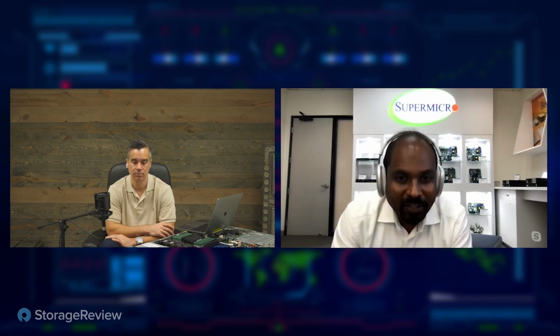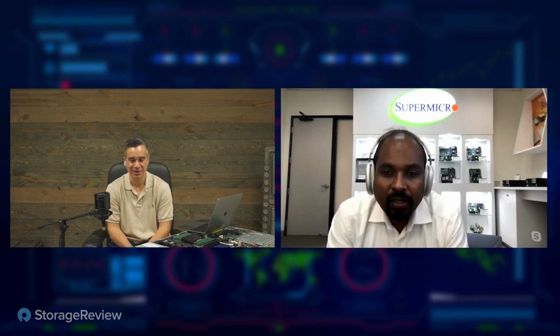Obviously, direct-to-chip liquid cooling is one of the things getting the most traction, mainly because you don't necessarily need chilled water. I mean, you definitely need to have water to the data center in order for us to use it. But the best part is that it's the least intrusive when it comes to managing the system. It fits into the standard rack, and as long as the plumbing is done properly, you can actually use it. We have deployed several HPC clusters, and we got the best practices figured out in terms of how to manage these things. You don't want anything to leak, you don't want anything to blow up. How do you do all those things, right? But that's just one part of it.